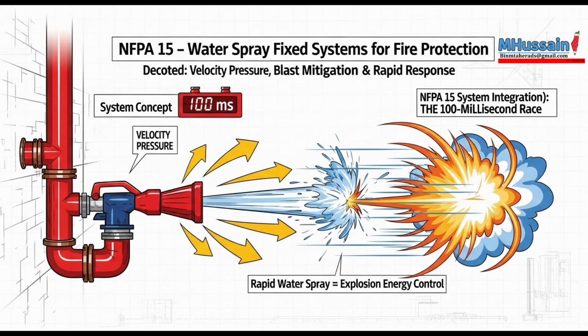Okay, finally, let's talk testing. Acceptance testing under 10.4.2 and 12.4. How does an engineer actually prove they met that seemingly impossible 100 millisecond target? For UHS systems specifically, that 100 millisecond response time has to be verified during acceptance tests, as required by 12.4 and 12.2.2. The AHJ will typically require specialized instrumentation, high-speed timers, flow switches, to precisely measure the time from the detector signal to confirmed water flow at the designated remote nozzle.